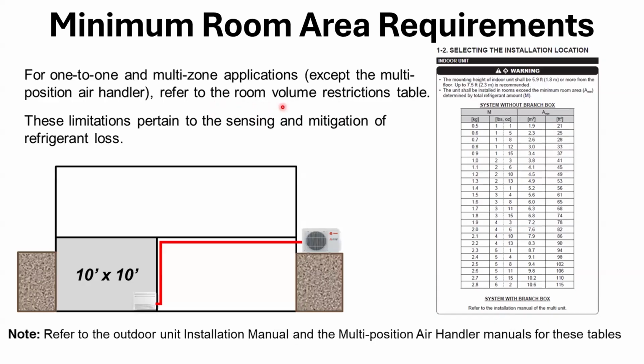So refer to the room volume restriction table out of the installation manual. You're going to have to read the install manual on these until you get the hang of them. These limitations pertain to the sensing and mitigation of refrigerant loss. That's why we have to do this. So again, refer to the outdoor unit install manual and multi-positional air handler manuals for these tables. What I would do is go to the SVZ install manual, where they have a worksheet, which I'm going to show you coming up next. That 2-page worksheet I would have on every job. And you'll see what I mean when I show it to you.